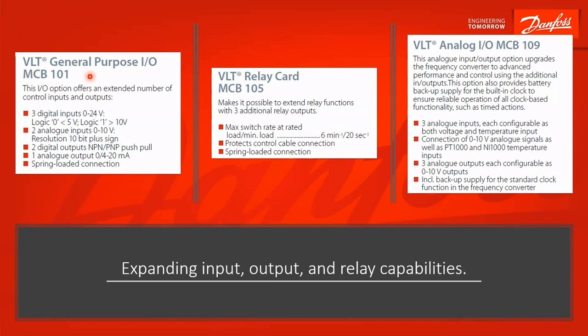The MCB101 — what does that add for you? You get three additional digital inputs, two additional 0 to 10 volt inputs, two additional digital outputs, and one more 4 to 20 milliamp output.